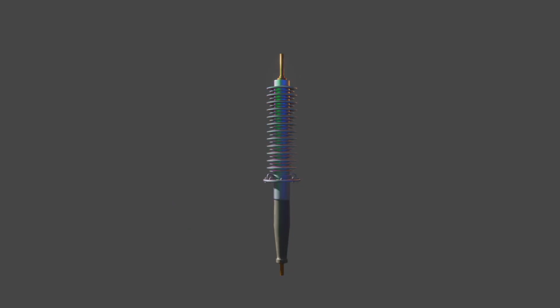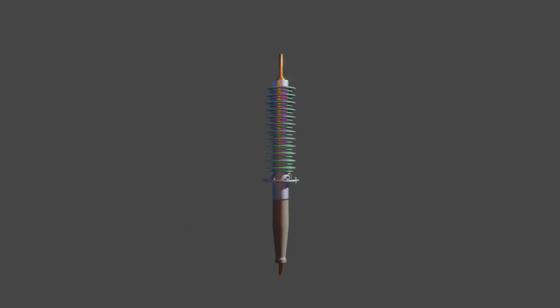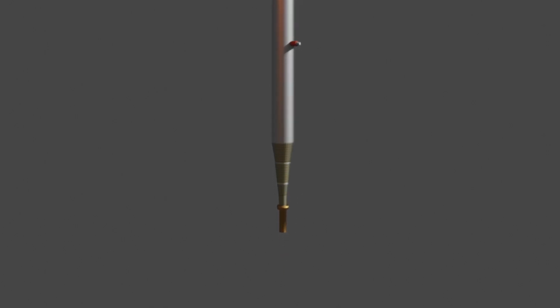First, imagine the innermost part of the bushing, a solid metal conductor, a copper rod or tube running through the center. This rod carries the high voltage current from the transformer winding out to the line. Around this metal rod are many layers of insulating material. In each layer, a sheet of aluminium foil is sandwiched between layers of dry kraft paper. Think of each foil paper sandwich as a little capacitor. All these capacitors are stacked in series, which makes the voltage drop evenly along the bushing.